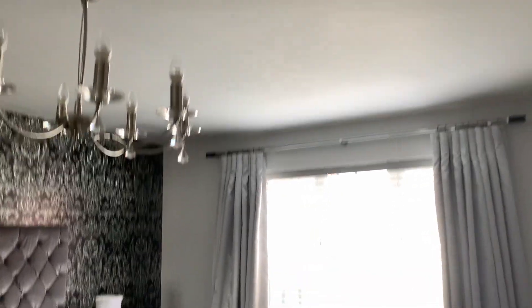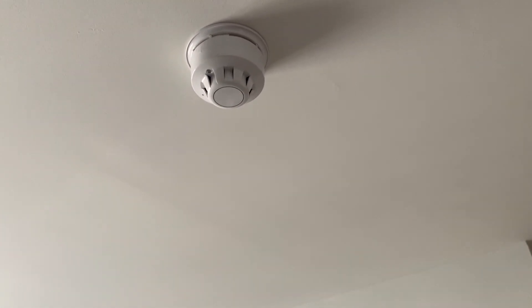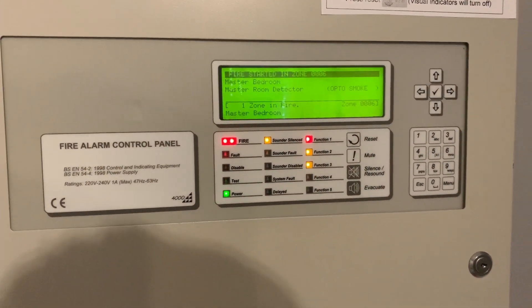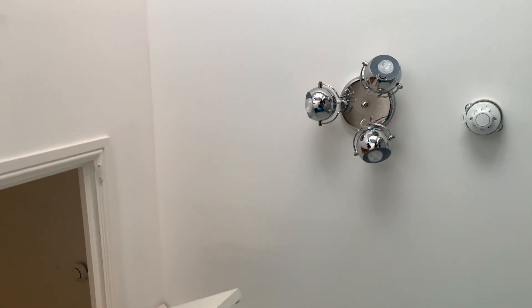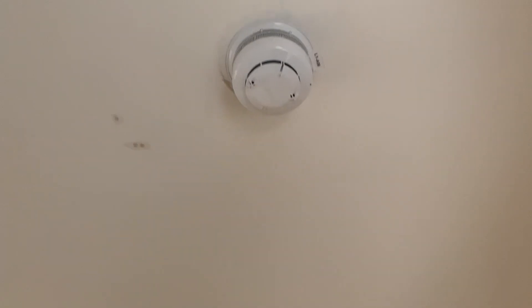Let's go to the side where the LED is. The investigation delay is off. That was quick — there you go, beacon. There we go, that works just fine, no issues with that. This VAD doesn't like to sync very well with that sounder base just there — it kind of just drifts out of sync. There we go, you can see that just re-synced. That looks very nice now.